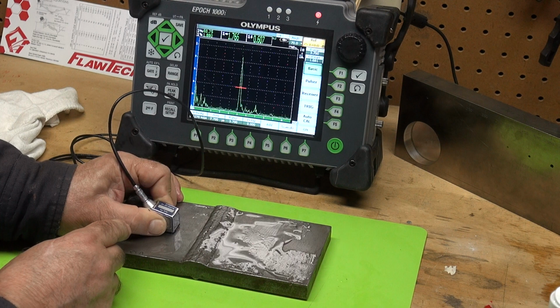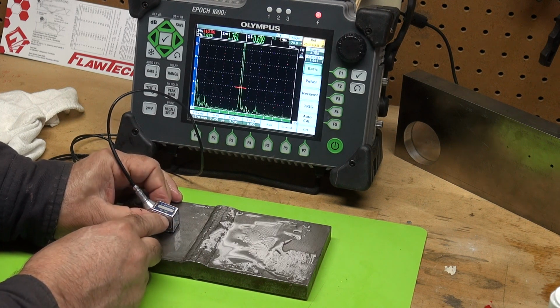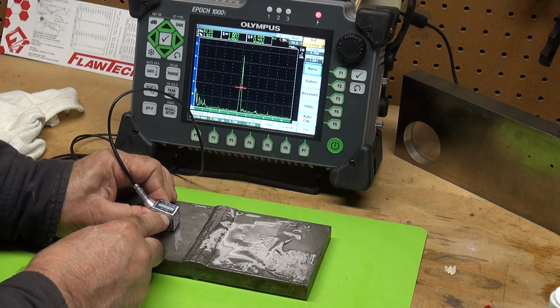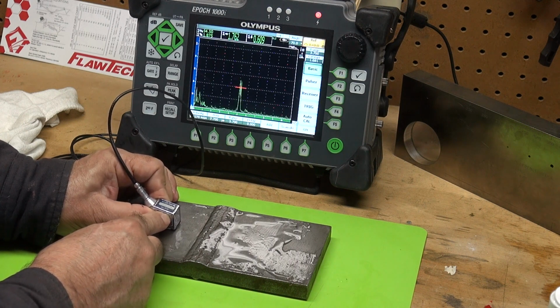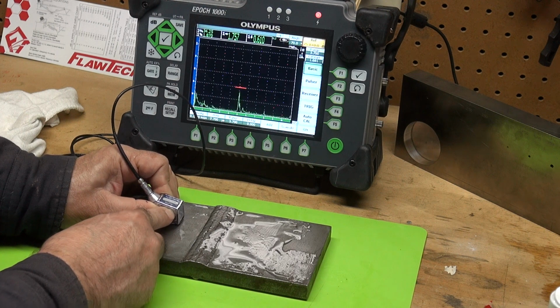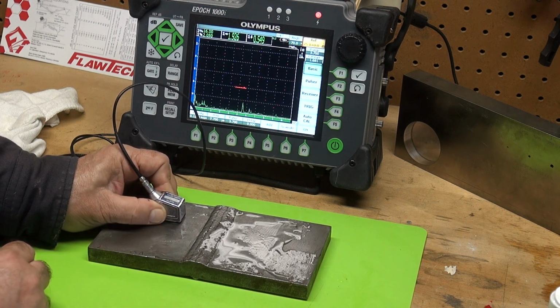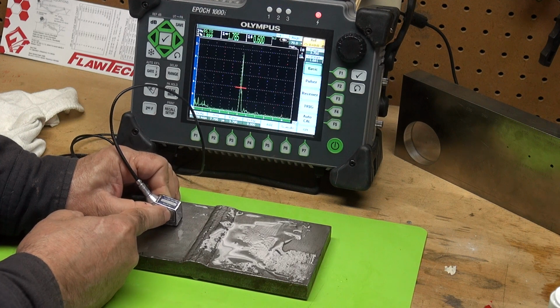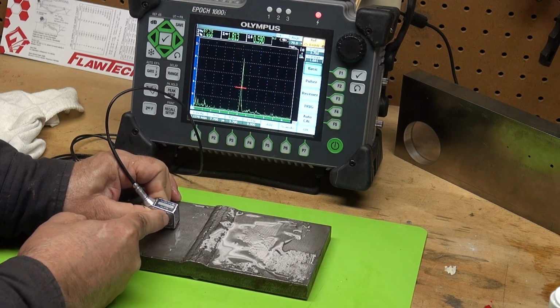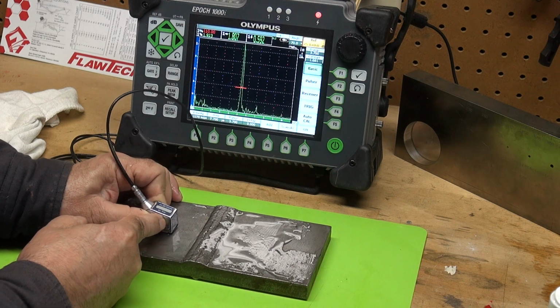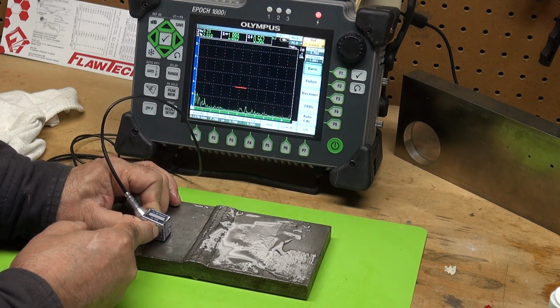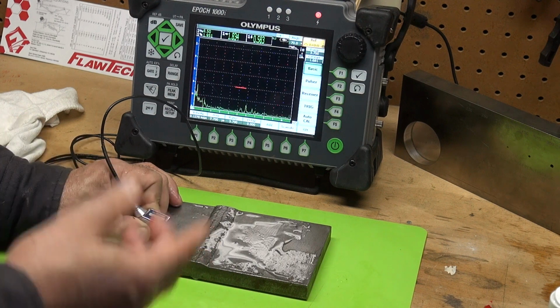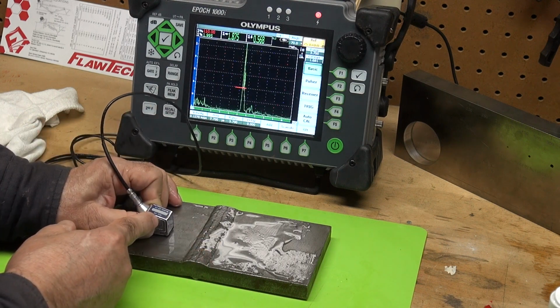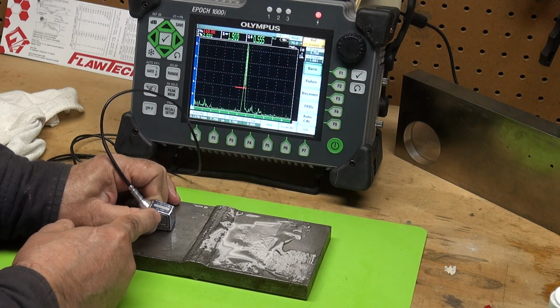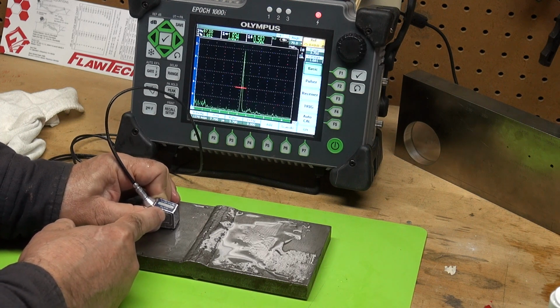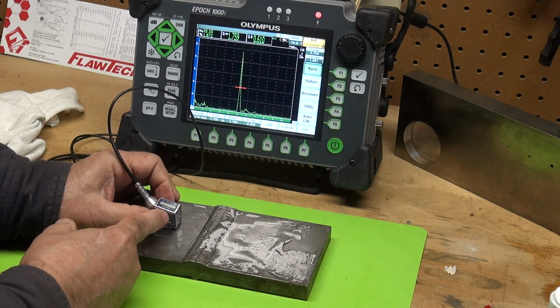See the facets. Let's look at the start stop. That's a very high amplitude signal. Move the probe away from us. See some of the facets? We're seeing facets of that crack. Boom. It's gone. We're out of the defect. We're in clean metal now. Let's come over into the indication, into the crack. Keep coming towards us, and then bang, goes away. Distinctive start stop. See it? Faceted. Plots right to the bottom of the weld.